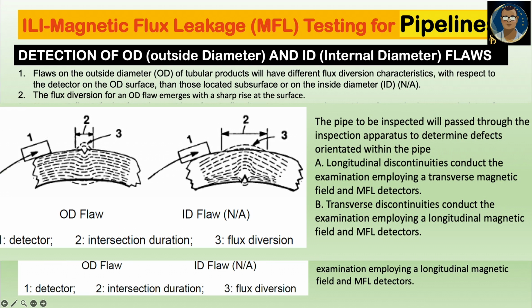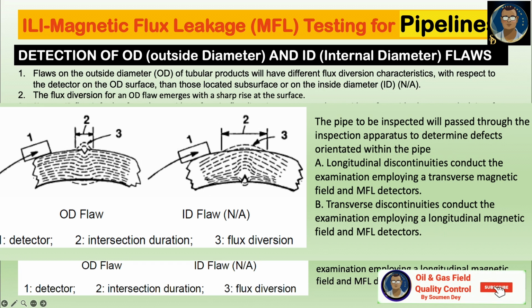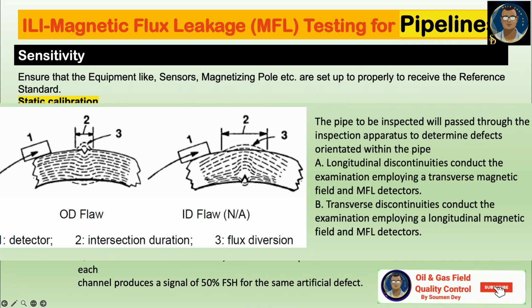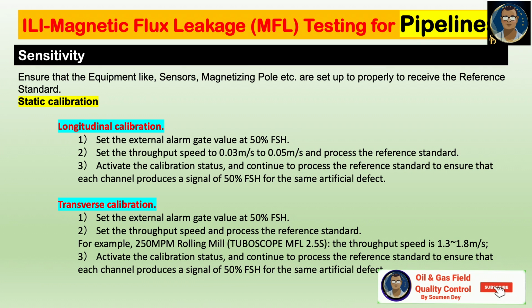Okay, the pipe to be inspected will pass through the inspection apparatus to determine defects oriented within the pipe. For longitudinal discontinuities, conduct the examination employing a transverse magnetic field and MFL detectors. For transverse discontinuities, conduct the examination employing a longitudinal magnetic field and MFL detector. Sensitivity: ensure the equipment like sensor, magnetizing pole, etc. are set up properly to receive the reference standard.